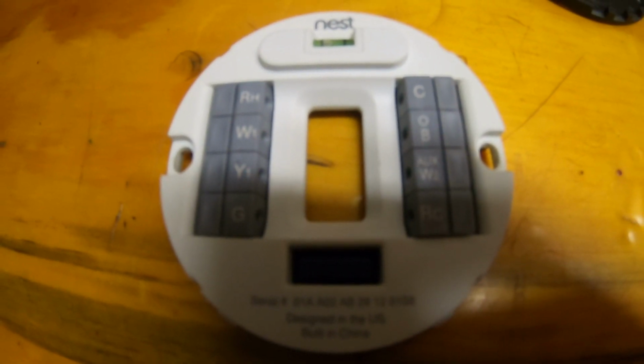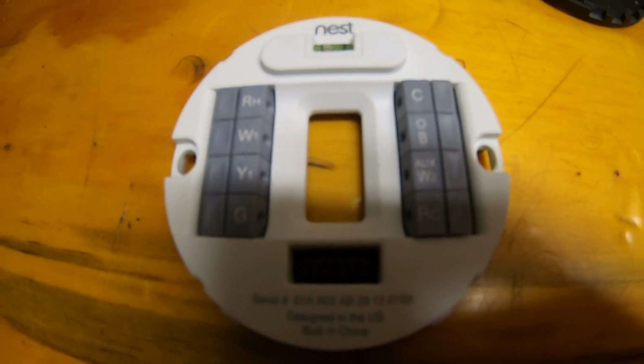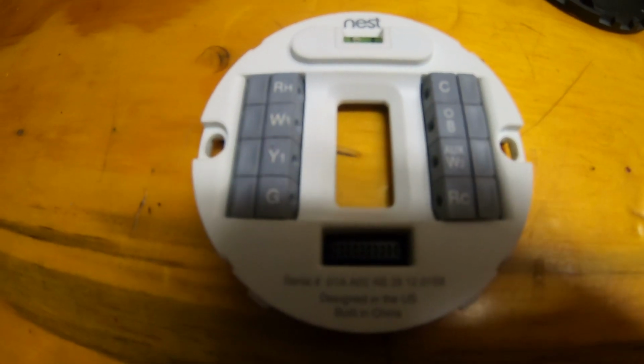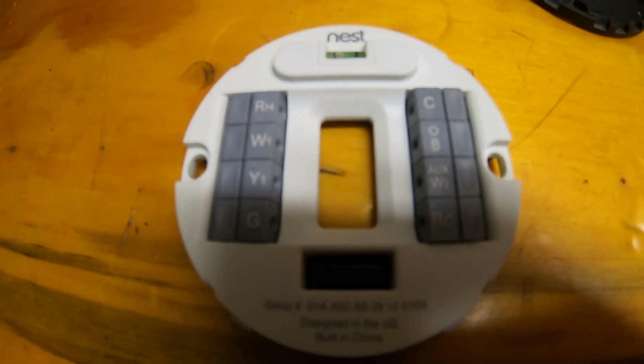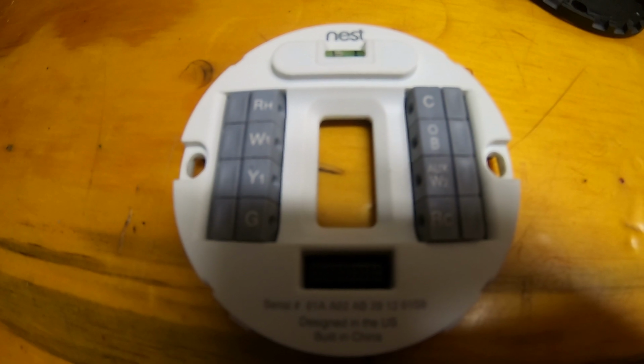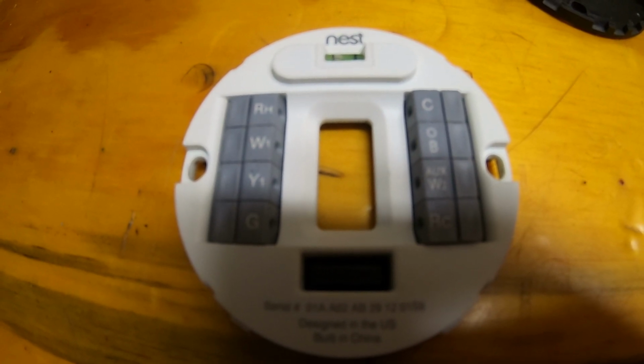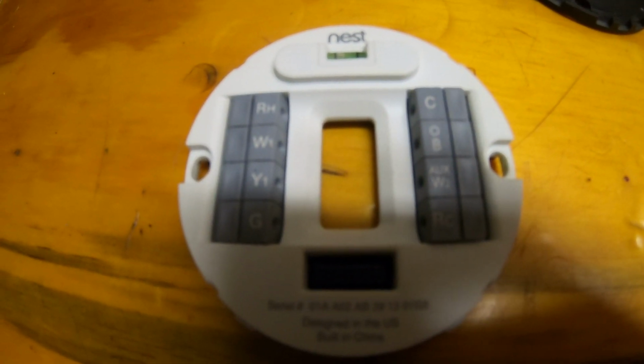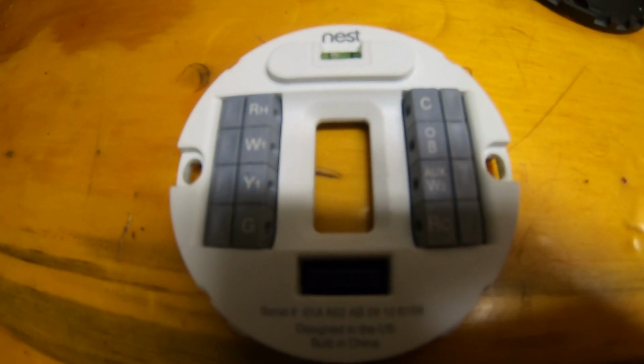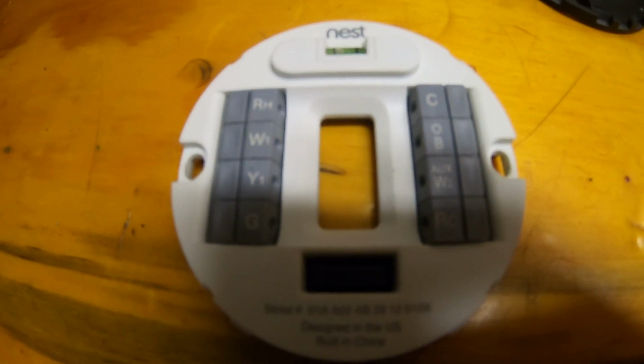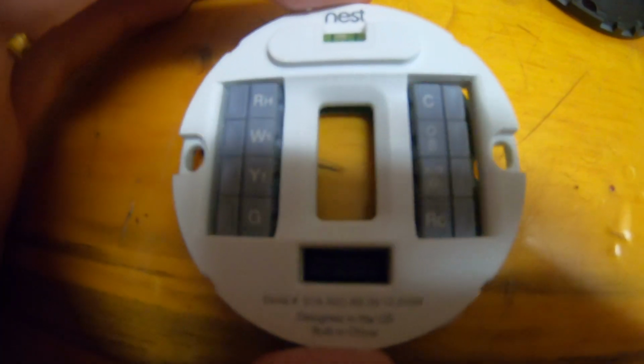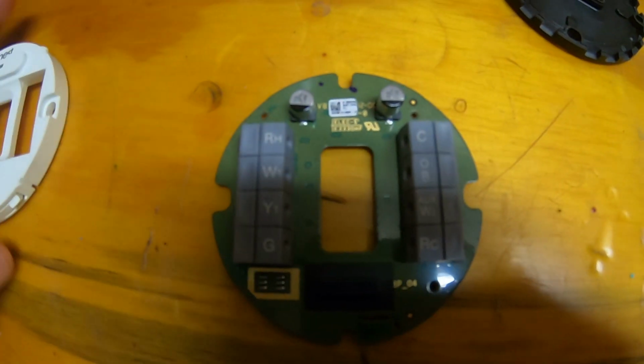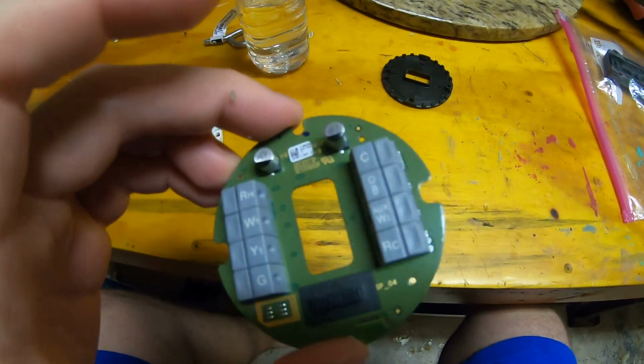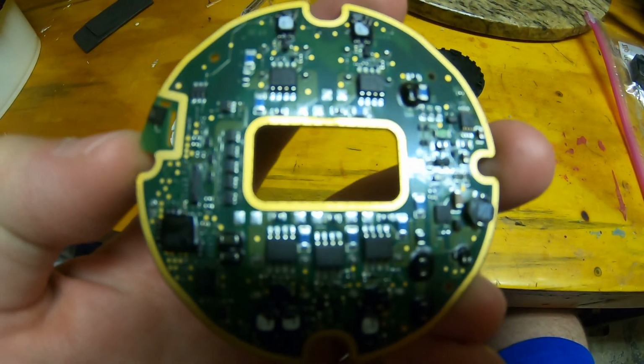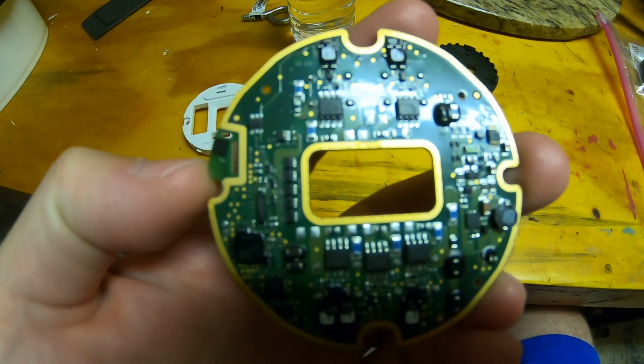He has also had another, this is a two-zone system. He's got, well actually it's two separate single-zone systems. He had an identical Nest thermostat on the other zone, so we took the Nest thermostat off the working zone and put it here, and we saw the same exact behavior, 16 volts. So I was kind of scratching my head, and then I looked at this plate carefully, and if you yank the cover off, this is a first generation Nest. You notice there's a printed circuit board here, and if you flip it over, there's a lot going on here for just a simple base plate.